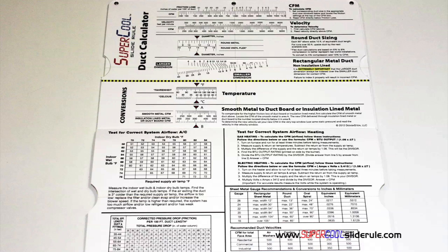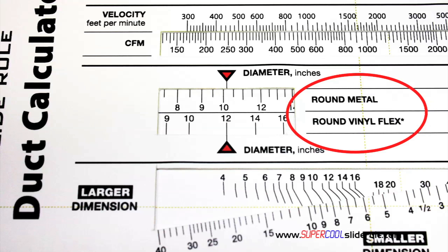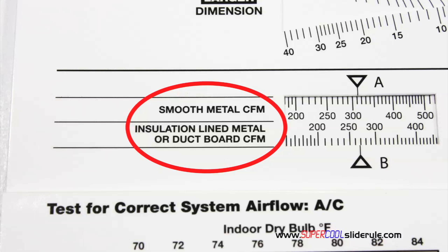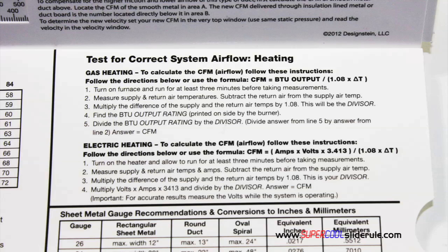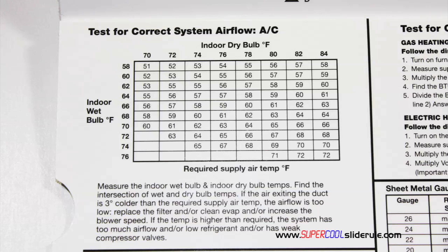Inside is packed with even more information. It performs sizing of both metal and flexible duct. It has the only direct reading conversion from smooth metal to insulation-lined metal we've ever seen. The majority of technicians have never been taught that if the insulation is on the inside of the ductwork, you cannot size it with a regular duct calculator. It has step-by-step directions for determining airflow through a gas furnace, electric furnace, or an air conditioning unit.